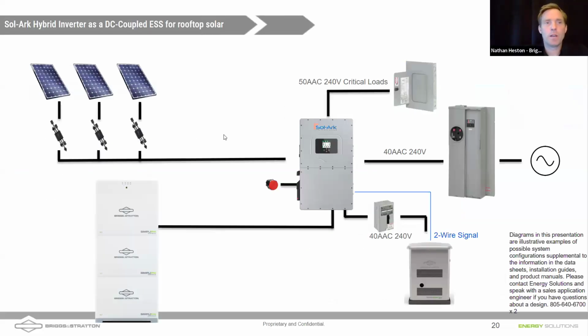Here's another example of a DC coupled Sol-Ark. These are rapid shutdown devices. If you have a rooftop solar array, you're going to be required to have a rapid shutdown device, and that's for safety reasons. So if you depress this red button, these are essentially switches that open up and shut the solar output down at the panel level. We bring these in as DC into the MPPTs of the Sol-Ark. The Sol-Ark then can use that energy to either power loads, charge the batteries, or send that excess power back out to the grid through the load center.